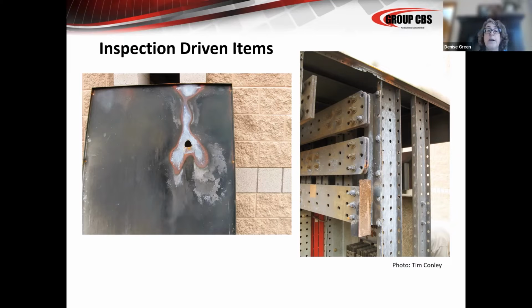having been inspected. They had a severe wind event, and the wind was strong enough to flex the center of the side panel in toward the bus. And the side panel breached the arc flash distance between the bus and the panel. And you had a phase to ground beginning fault that turned into a phase to phase fault. And you can see the melted structure above, in addition to the hole welded in the side. So that maintenance component, when you're not only taking care of circuit breakers, but looking at the gear itself, is important to make sure that even initial installation problems are caught down the road so that something like this doesn't happen.